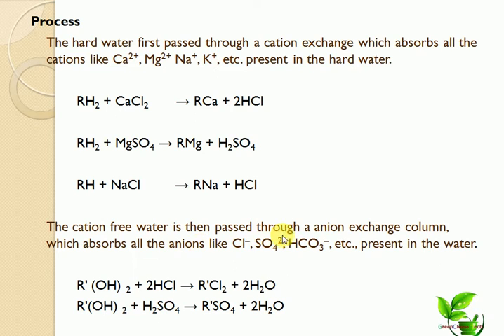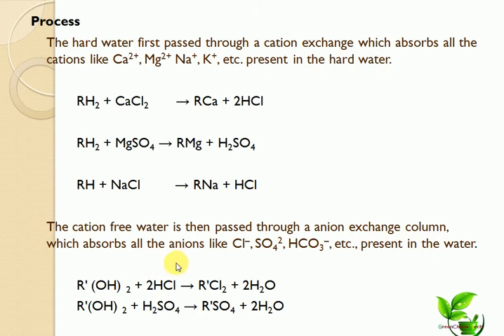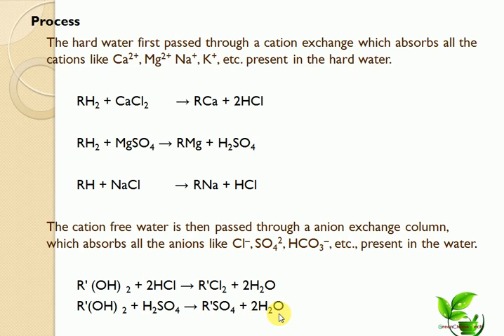The cation-free water is then passed through the anion exchange column, which absorbs all anions like chloride, sulfate, and bicarbonate. The anionic resin, represented as R(OH)₂, reacts with HCl: R(OH)₂ + 2HCl → RCl₂ + 2H₂O. Similarly, sulfuric acid reacts with anionic resin: R(OH)₂ + H₂SO₄ → RSO₄ + 2H₂O.